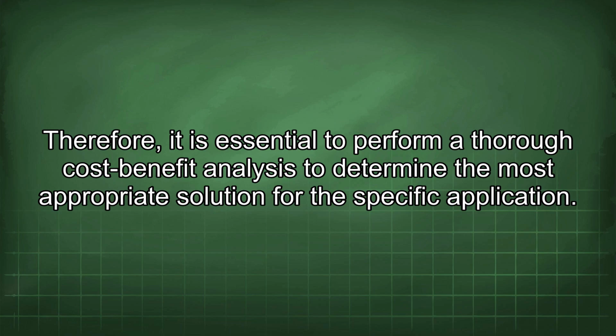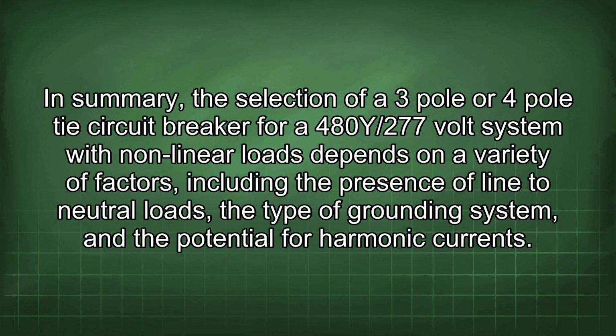Therefore, it is essential to perform a thorough cost-benefit analysis to determine the most appropriate solution for the specific application. In summary, the selection of a 3-pole or 4-pole tie-circuit breaker for a 480Y/277V system with nonlinear loads depends on a variety of factors, including the presence of line-to-neutral loads, the type of grounding system, and the potential for harmonic currents.